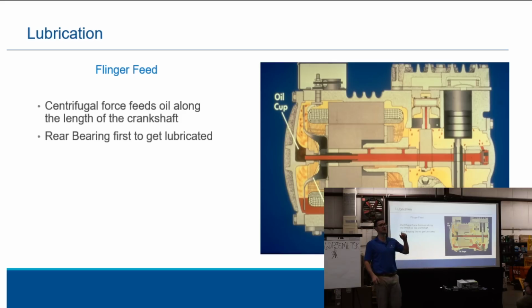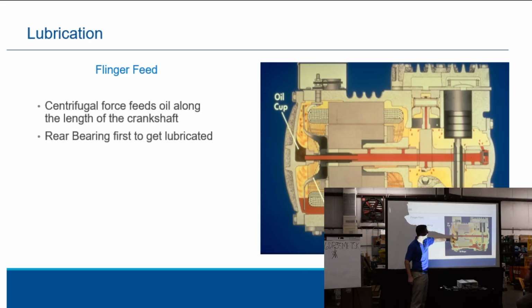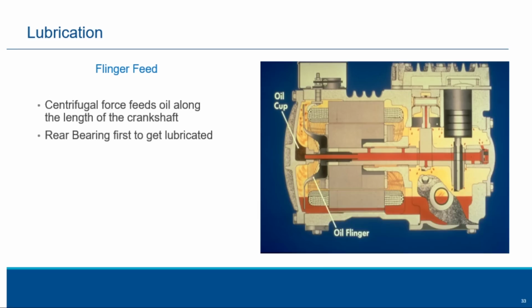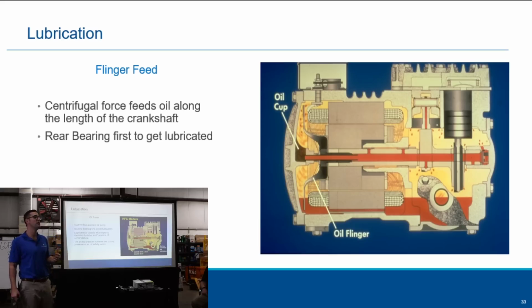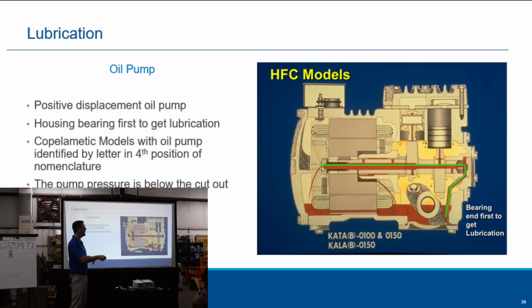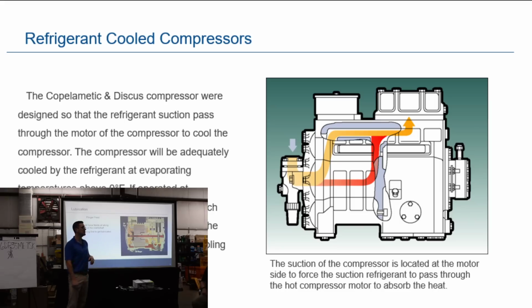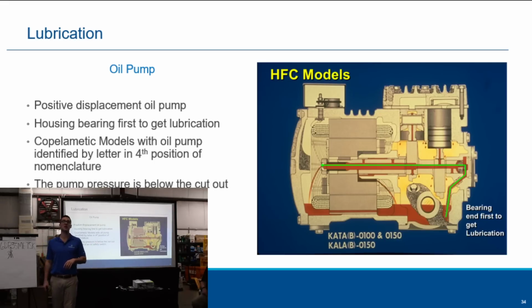Flinger feed. There are two types of oil feeds in this style of compressor. You have the flinger, which is mounted onto the crankshaft, and it spins as it hits the oil and splashes up into this cup and lubricates the bearings. We moved on to an oil pump version, as you can see here, when we got into the higher pressure refrigerants like HFC refrigerant. We were having a lot of failures at the bearing right here, so we developed an oil pump. And now what this oil pump does is pull up the oil and lubricate all the bearings.